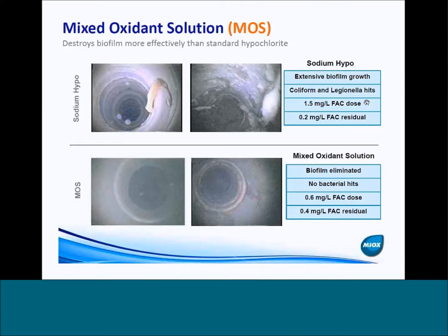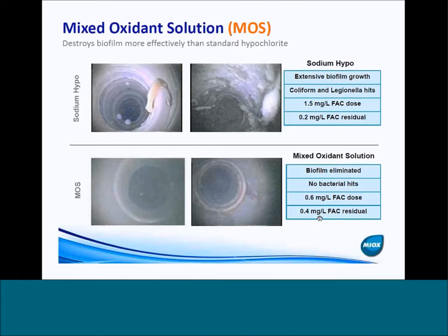They were dosing pretty high levels — one and a half milligrams per liter at their injection point — and were only seeing about 0.2 milligrams per liter free available chlorine residual. This is a little less than a month afterwards when they had switched over to mixed oxidant solution. You can see there's really no biofilm left in the pipes, and they got no bacterial hits. They were actually able to drop their dose by over half to 0.6 milligrams per liter, but they doubled their free available chlorine residual. In a potable water distribution system, you'd have quite a bit less disinfection byproducts because you're lowering your dose as well as your organic load.